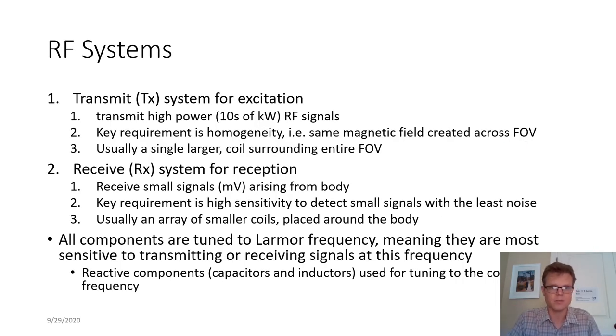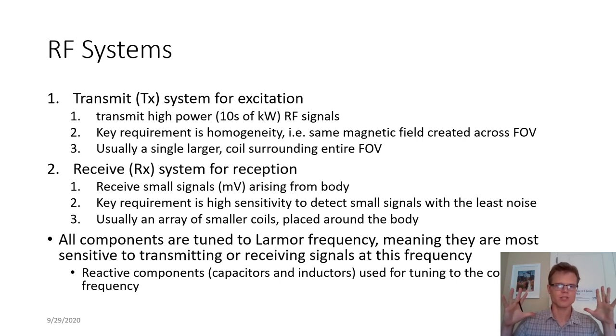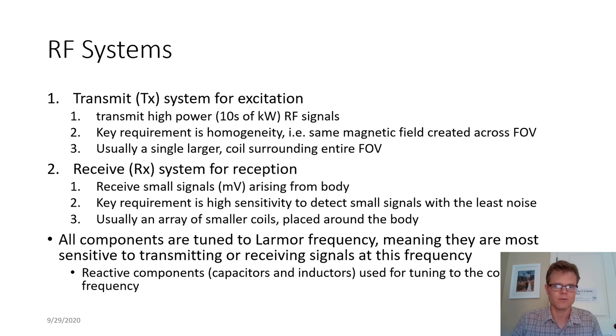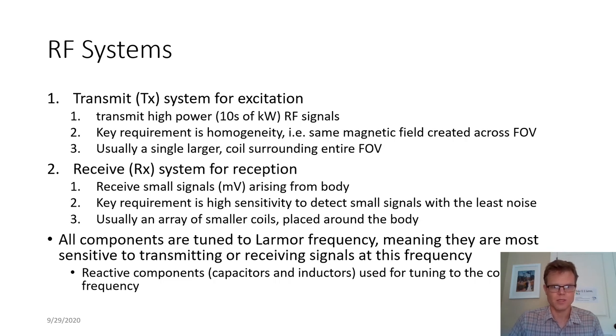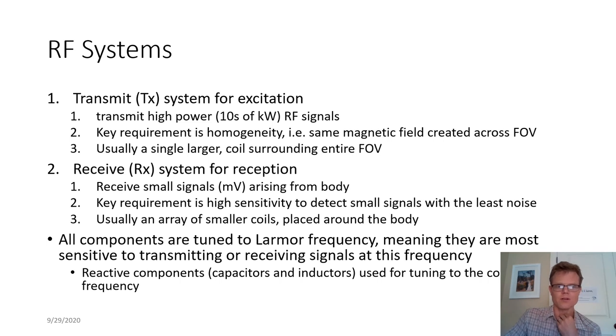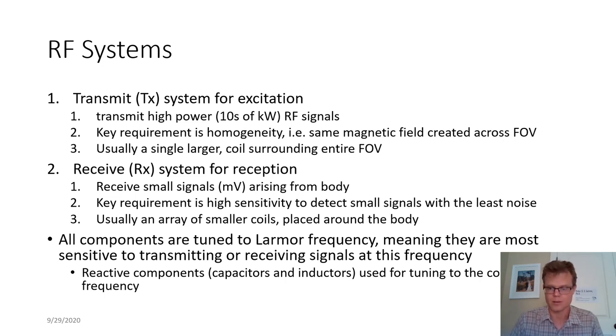The transmit system, sometimes abbreviated TX, operates at very high powers — like tens of kilowatts — and we want this to be homogeneous across our entire subject. Usually it's done by a single large surrounding coil, typically called the body coil. The receive system is trying to detect these small currents in the millivolt range that arise from the net magnetization in the body. Since these are small signals, the most important thing is sensitivity, so it's better to create small loops and put them right on top of the subject. Everything here is tuned to the Larmor frequency — the specific radio frequency — by the electronics, capacitors, and inductors in these RF coils.